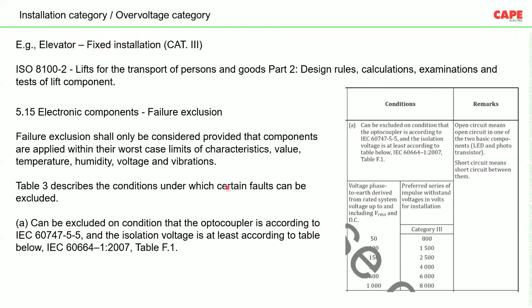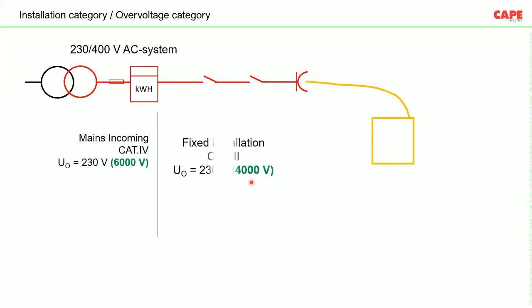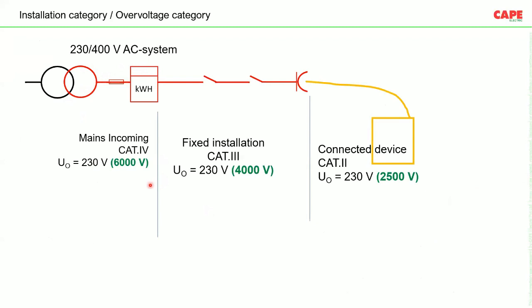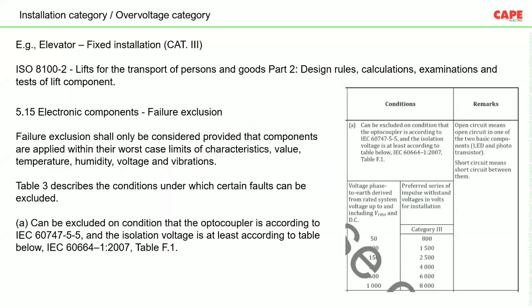So, in one moment, I will show you. Yeah, here, these are the categories. At the mains incoming, category 4 device. At the fixed installation, that means your wiring is fixed. The sub switch board, the wiring, the fixed installation such as equipment like a fan, equipment like a light fitting. These are not pluggable. These are fixed equipment. Then for connected devices, you see here 2500 volt, 4 kV, 6 kV. These are the voltage impulses which are mentioned. Now, a lift is a part of a fixed installation.